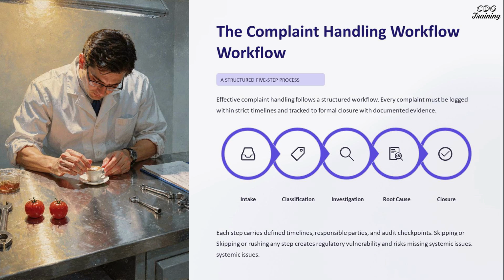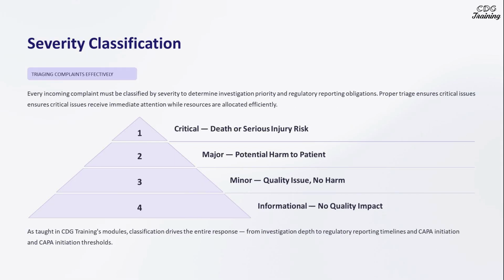Effective complaint handling follows a structured five-step workflow: initiate, classify, investigate, find the root cause, and close. Each step is crucial to prevent regulatory vulnerability and systemic issues. Every incoming complaint must be classified by severity to determine reporting priority and regulatory obligations. Proper triage ensures critical issues receive immediate attention while resources are allocated efficiently. Serious complaints must be reported to regulatory authorities within strict timelines. Immediate notification is required for life-threatening events, ensuring swift action to mitigate risks.